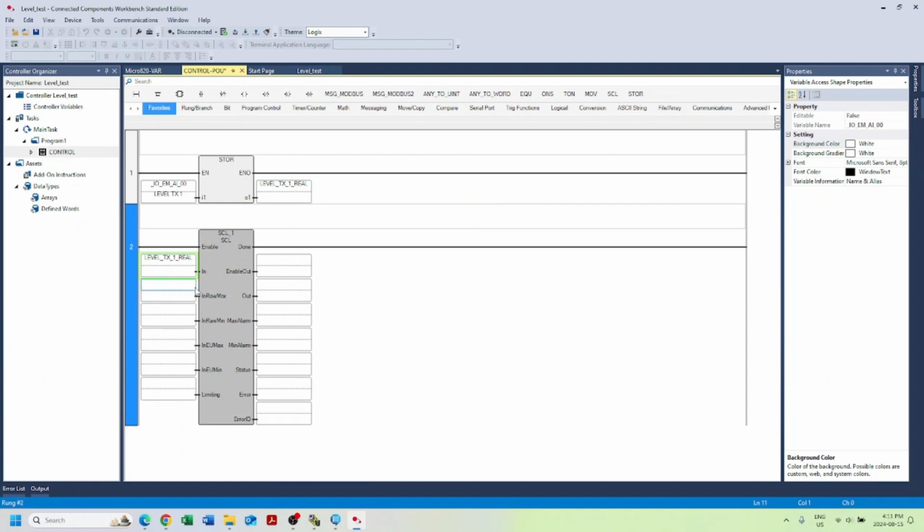So there are a few different ways to figure out what your input raw max and input raw minimum are going to be. However, the easiest way to do it, I find, is trial and error. If you just stick a multimeter in there. For these, I know that I'm somewhere for a 4 to 20 transmitter with the way we have it configured with the resistors, because I put a 250 ohm resistor from the common to input number 1. I just know from experience, and again, we're going to go back to this.